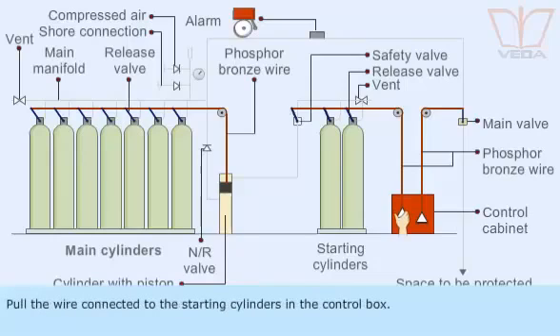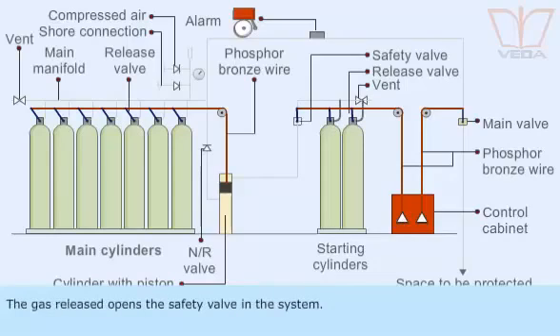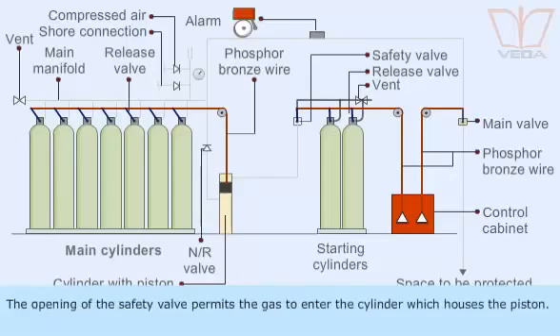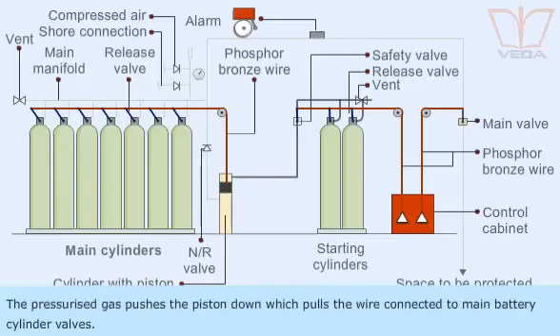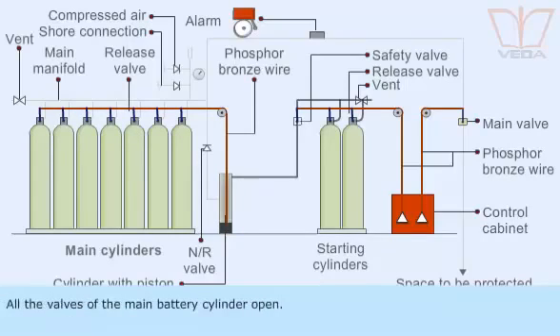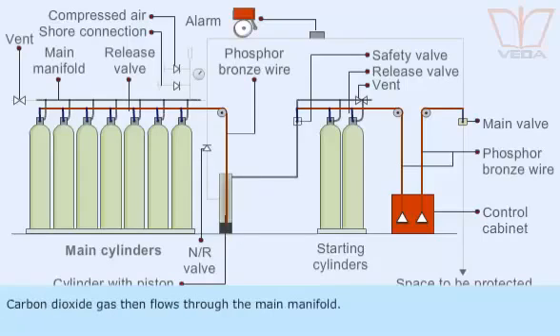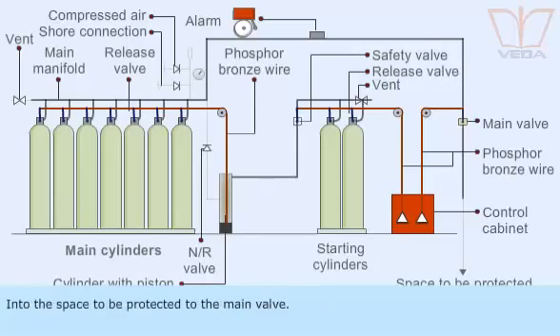Pull the wire connected to the starting cylinders in the control box. The gas released opens the safety valve in the system. The opening of the safety valve permits the gas to enter the cylinder which houses the piston. The pressurized gas pushes the piston down, which pulls the wire connected to the main battery cylinder valves. All the valves of the main battery cylinder open. Carbon dioxide gas then flows through the main manifold into the space to be protected through the main valve.